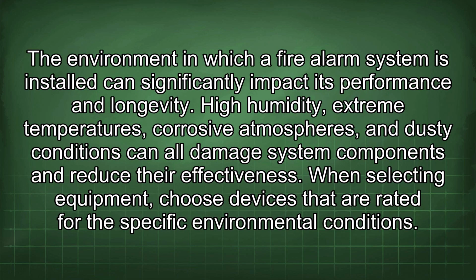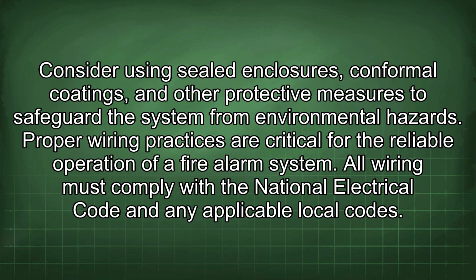The environment in which a fire alarm system is installed can significantly impact its performance and longevity. High humidity, extreme temperatures, corrosive atmospheres, and dusty conditions can all damage system components and reduce their effectiveness. When selecting equipment, choose devices that are rated for the specific environmental conditions. Consider using sealed enclosures, conformal coatings, and other protective measures to safeguard the system from environmental hazards.